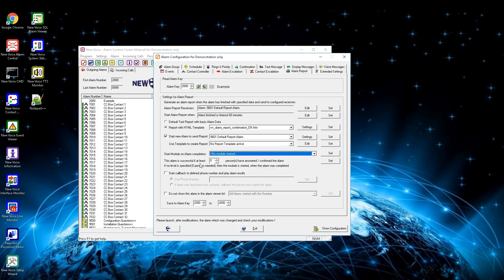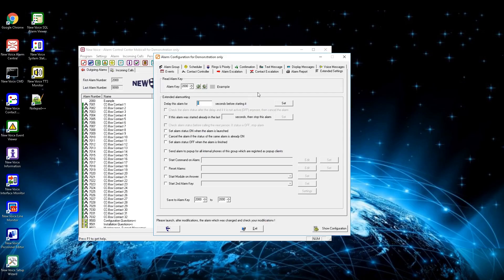With the drop-down menu start module on alarm completion, you can define a module that will update a third-party system. Below, set the amount of persons needed for this alarm to be considered successful. By the checkbox below you can activate calling a defined phone number or the initiator to play the alarm report. The last checkbox prevents this alarm from being shown in the SQL alarm viewer. Within the extended settings you have several options: the first is to delay this alarm for an amount of seconds before it starts. When a delay is given, you can also check the alarm status after the delay and cancel if it is no longer active.